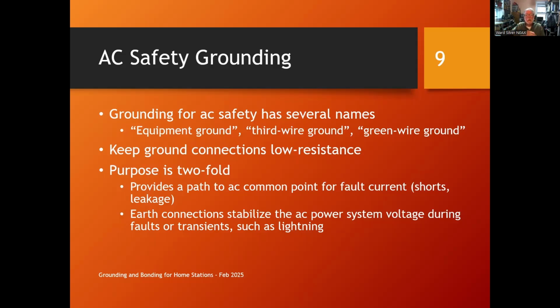Got to keep your ground connections good when you're talking about AC safety. The most important thing is they be low resistance. Remember, I talked about that ground connection has to carry enough current if there's a fault so that the protective device at the other end will open up and remove power from the affected circuit.